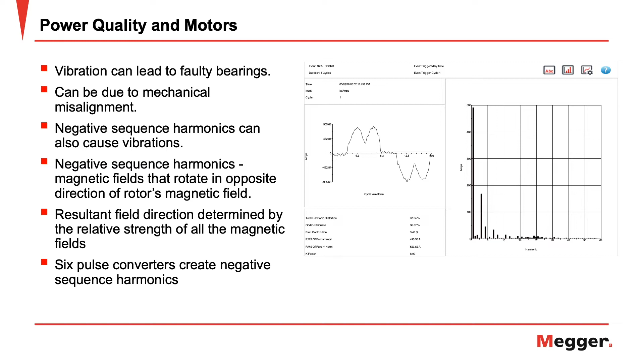Negative sequence harmonics are harmonics that have magnetic fields that rotate in the opposite direction of the rotor's magnetic field. The negative sequence components can produce a resultant field or vector field. The direction of this field will be determined by the relative strength of all the magnetic fields, and this can lead to motor vibrations. Negative sequence harmonics are a byproduct of 6-pulse converters, which are commonly found in 3-phase power supplies, and these are often used in variable frequency drives or VFDs.